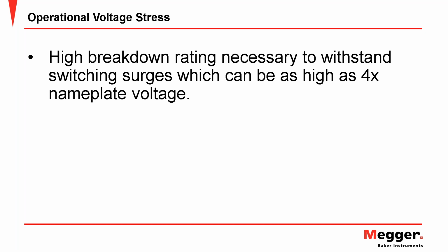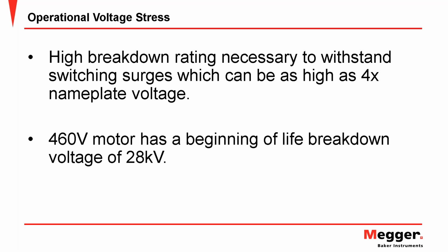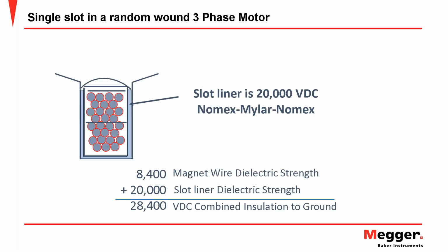So as I mentioned before, operational voltage stresses, high breakdown rating is necessary to withstand the switching surges, which can be as high as 4 times the nameplate voltage. As an example, a 460 volt motor at the beginning of its life has a breakdown voltage of 28,000 volts, and we saw that in the graph. And this is where we get that number. If you look at that individual slot, the enamel coated wire, this is a random wound motor. 460s are typically random wound, or mush wound, sometimes they're called. That randomness refers to the geometry, so turn one isn't necessarily next to turn two. There's no fixed geometry.